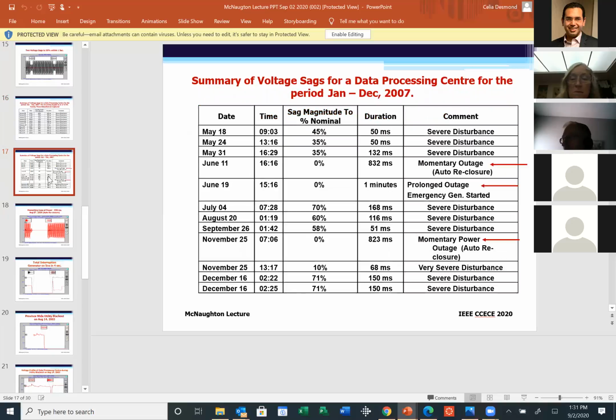What I want to point out with an arrow is the one on June 11, as you can see on the slide. We have what we call a momentary outage. What this means is this site will experience total loss of power for less than 1 second, 832 milliseconds, and the power was restored. However, the event that took place on June 19 was a prolonged outage, meaning the power was lost, it didn't come back.